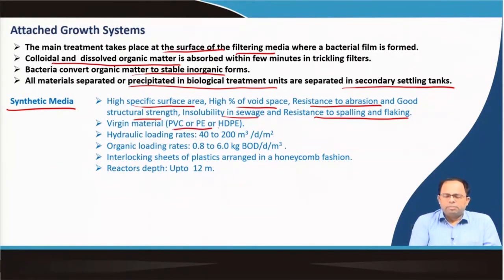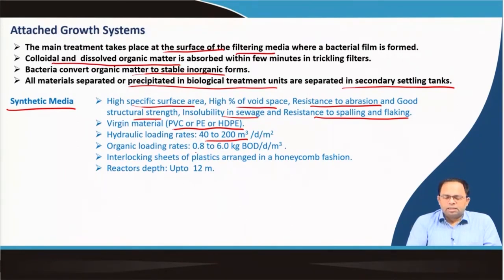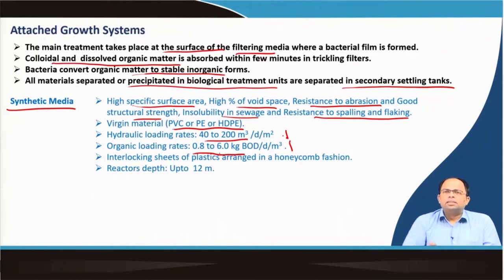The media used today is typically synthetic, designed to have very high specific surface area, high void percentage, resistance to abrasion, good structural strength, insolubility in sewage, and resistance to spalling and flaking. It is usually made of PVC, PE, or HDPE. Hydraulic loading rates are around 40 to 200 m³/day/m², and organic loading rates are 0.8 to 6.0 kg of BOD per day per m³.